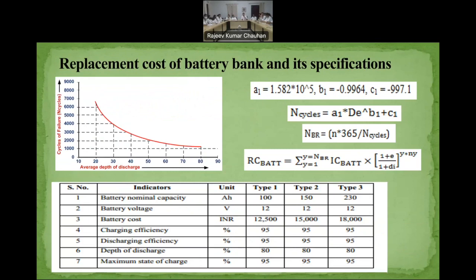Now this is a very interesting point that I will cover: the replacement cost of the battery bank and its specification. This is very important - you can see the data of depth of discharge versus cycle of failure. Your batteries have a limitation; you have to replace the battery depending on the state of charge at which you are operating.